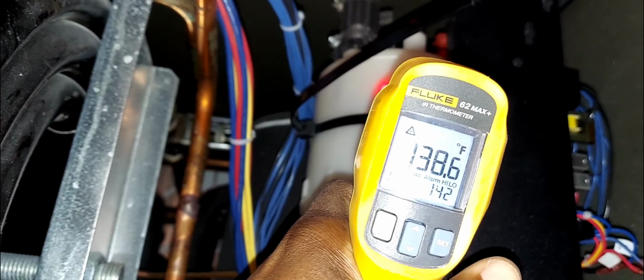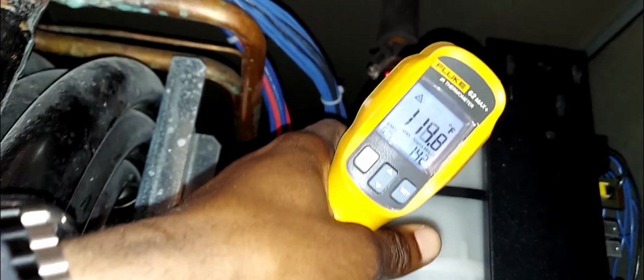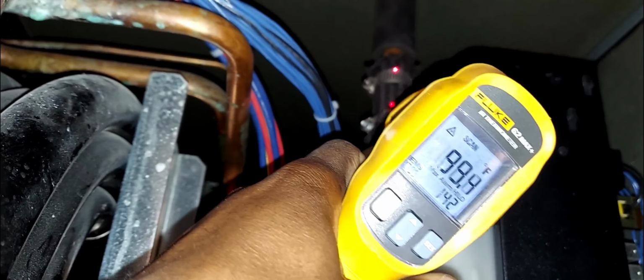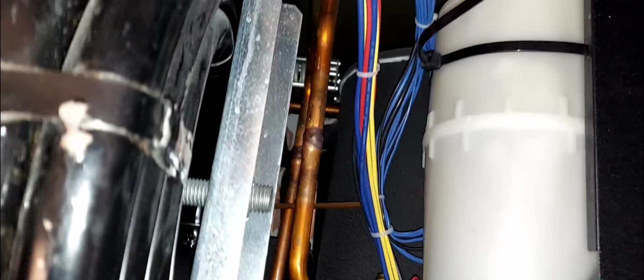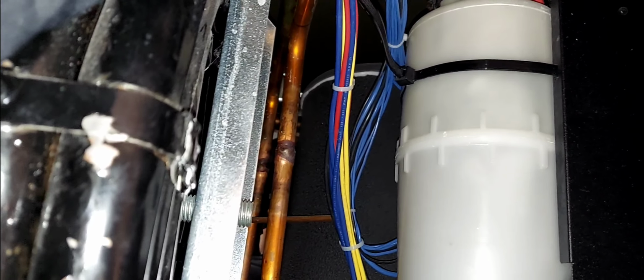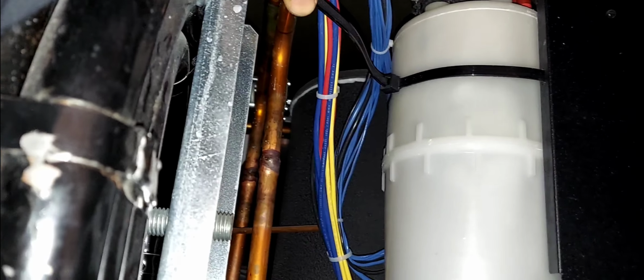So I was scanning. You see the canister is hot right now. It's boiling. All right, so it's making humidification, right? It's doing humidification. So there's water in this canister, and there's electrical probes suspended into the water, and once the current flows between these electrodes or probes, it creates heat in the water, and the water boils, and that's how you get humidification.